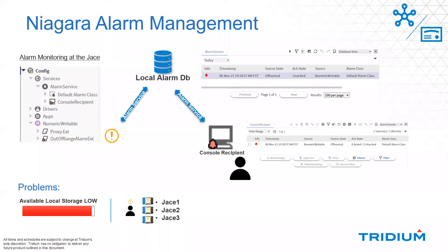At any given time, if you want to see what's currently happening in the database, you have the database view at the top right. That is a view of the alarm service component itself. You can't do much in that view other than see everything — it's not the way the user interacts with the alarm. The way a user interacts with the alarm is through a console recipient. You can tie alarm classes to a given console recipient. A user can acknowledge an alarm — meaning 'I've seen this come in, I know it's a problem, and I'd like to acknowledge that I've seen it.' When you acknowledge an alarm, if the condition is still in alarm, it will reside there on the console recipient waiting for you to address the problem.